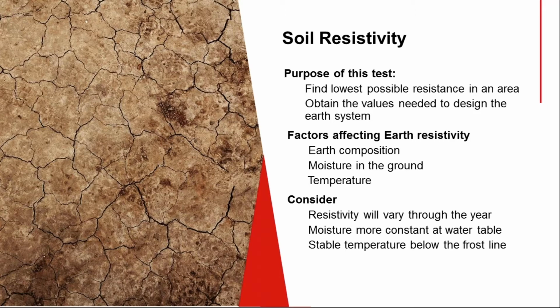The average moisture content is important, but also the moisture content around the calendar. In most areas, the best times of year are spring and fall. Winter and summer tend to be more demanding. You don't want a ground that meets spec in spring, then a hot, dry summer comes along, it goes out of spec, and something happens and you lose equipment. So be careful of that.